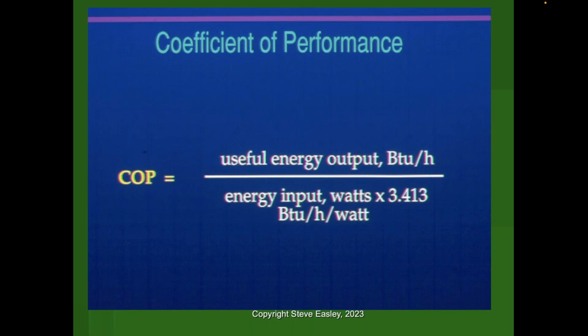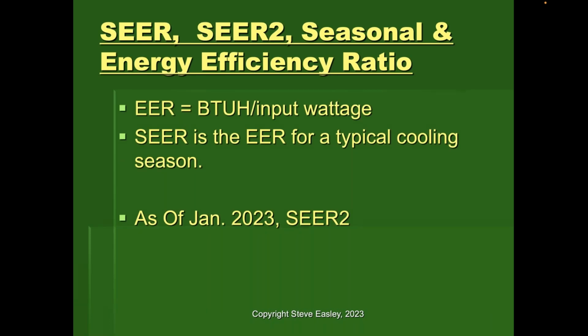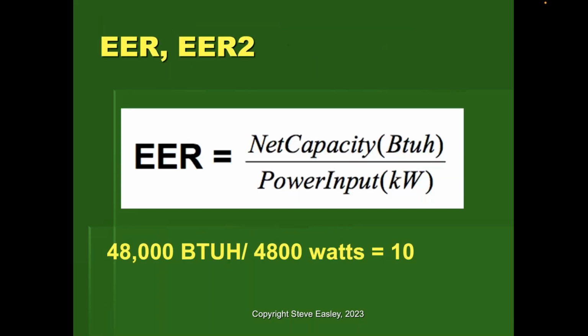So again, the coefficient of performance, if you're interested in this later, you can review this presentation because it's going to be recorded. It's basically the useful energy output in BTUs per hour divided by the input in watts times 3.413 BTUs per watt, if you're interested in those technical details. So when we talk about SEER or SEER2, that's typically what we're referring to for air conditioning efficiencies. So EER is simply the BTUs per hour divided by the input wattage, and SEER is that for the entire cooling season. Now, for those of you that are out in the Midwest and out east, SEER2 is probably the most important number to remember when you're selecting an air conditioning system. But if you're out in the West, we care more about EER or EER2. So EER is simply the net capacity in BTUs divided by the power input. So it's real simple. If I've got a 4-ton unit or a 48,000 BTU per hour system, and it takes 4,800 watts to operate that, it has an EER of 10.